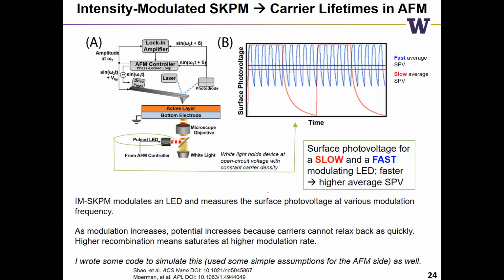But going from Kelvin probe to another technique we can do, this one's called intensity-modulated scanning Kelvin probe, and it's something we haven't done in a while. One of the two people that actually did it is Micah, who runs the AFMs in MAF, so you can always go talk to him about it. In the instrumentation schematic, the top part is the same as Kelvin probe. The bottom part is what's different. Instead of applying a single static light source, like you might to just measure photovoltage, where you turn on a light and then measure the Kelvin probe image, you're modulating the light. And if you want, you can hold the device at a particular open circuit by applying a white light bias of a particular intensity. As you modulate this bias, you're measuring the surface photovoltage. When you measure surface photovoltage, that's an average measurement.